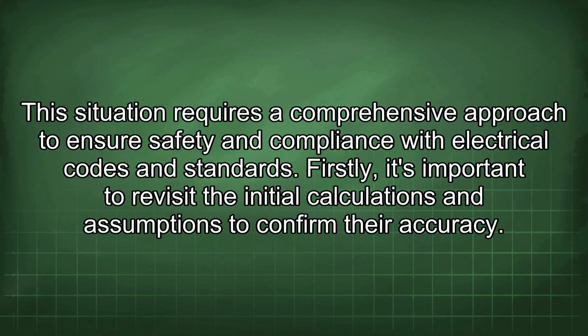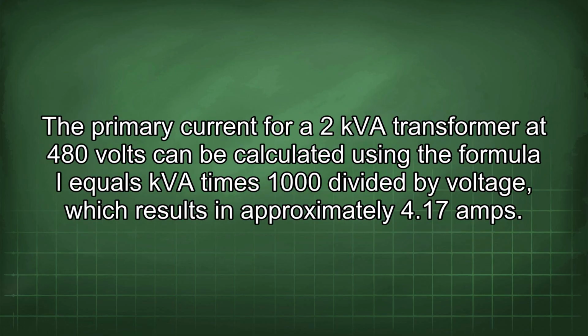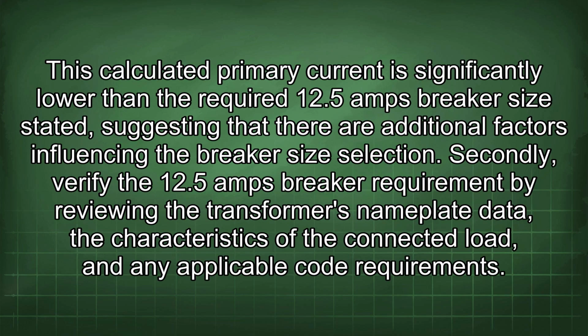Firstly, it's important to revisit the initial calculations and assumptions to confirm their accuracy. The primary current for a 2 kVA transformer at 480 volts can be calculated using the formula I equals kVA times 1000 divided by voltage, which results in approximately 4.17 amps. This calculated primary current is significantly lower than the required 12.5 amps breaker size stated, suggesting that there are additional factors influencing the breaker size selection.